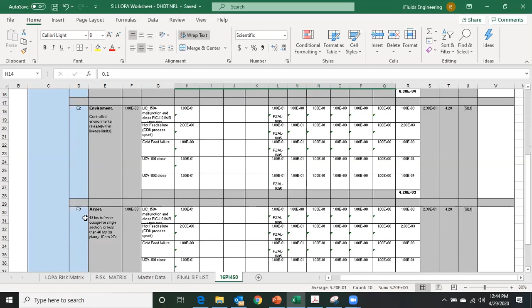Okay. Sometimes you will have a less effect on the people and you may have a more effect on the asset, if you are having a furnace. That may require SIL 2 also. Okay. Most of the times it will be people, and almost you can say 40 to 60% of the time SIL 2 with the higher rate of SIL with respect to people, and 40% of the time with respect to the asset. Okay, environment with respect to refinery petrochemicals, it will not be that much. If it is acid plants or anything, or if the discharge is going to the river or anything, environment will come in. There it may require higher SIL rating.